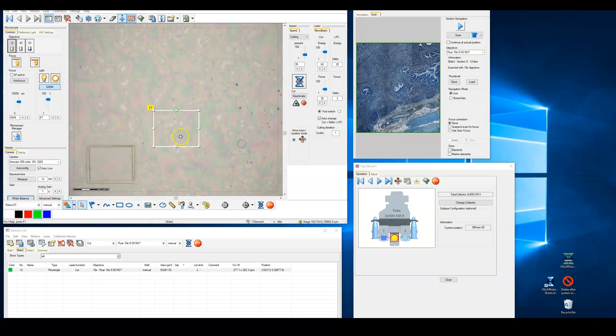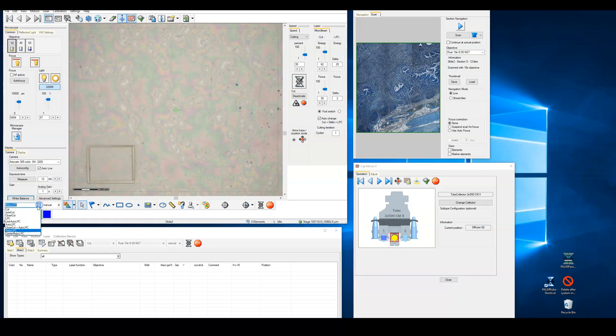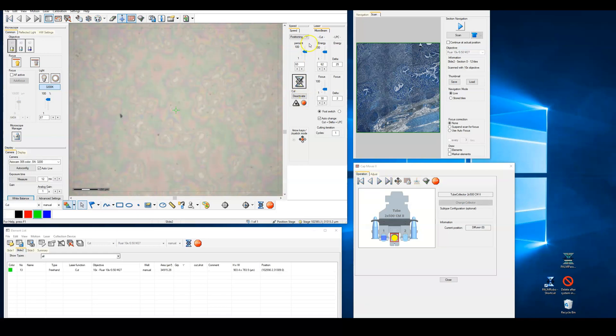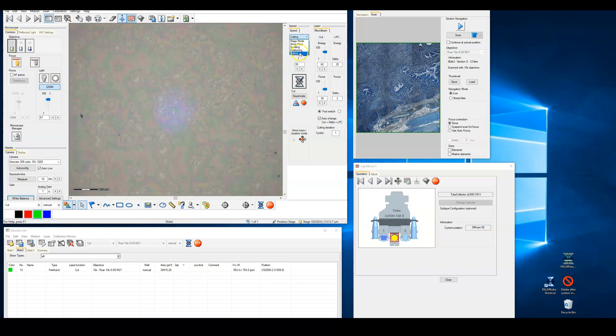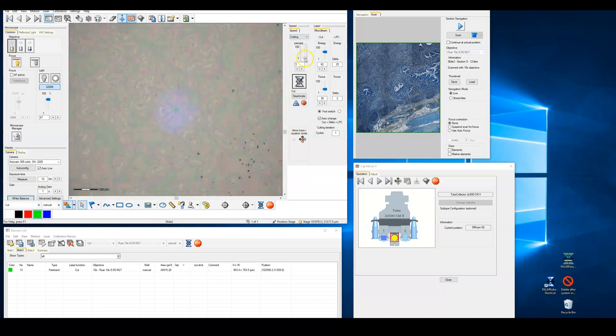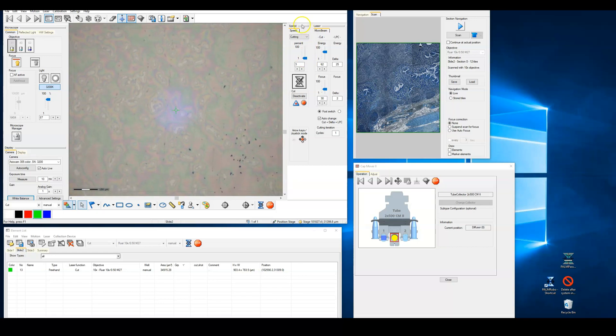In order to adjust the cut laser, begin by changing the cut type on the main window to simply cut. Now draw a winding path in the live image and start the cut of this element. If you had any other elements drawn, it's best to delete these before starting. As you watch the laser travel along the cut line, you may want to change the speed of the cut to make the process easier for you the first time. You can do that under the speed menu to the right of the image.